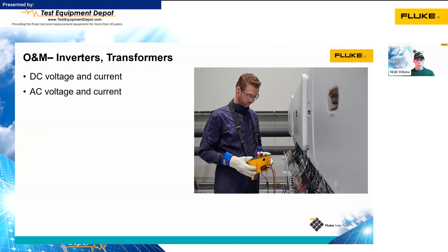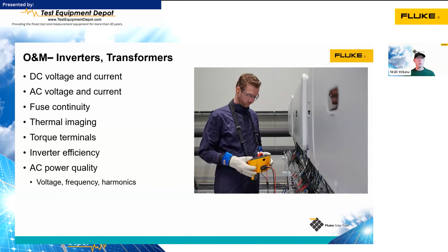Our inverters and transformers are going to need operations and maintenance as well. We can do simple things like AC and DC voltage and current testing. We can check our fuses to make sure that they have not blown. We can do thermal imaging to see if there's any hot spots or cold spots. We can also torque our terminals. That's not a tool that Fluke sells, but it's really important to make sure that the terminals are properly torqued.